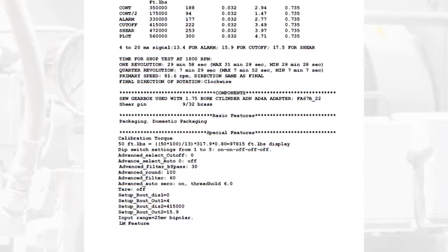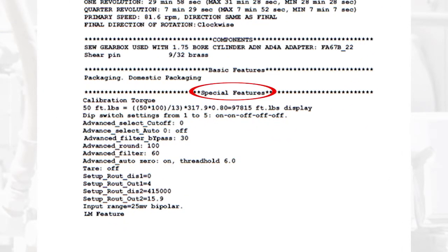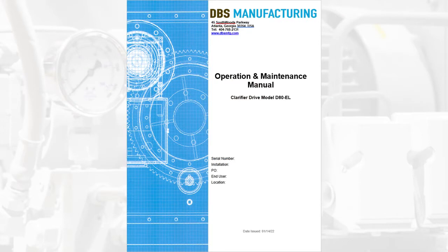The 2 numbers you will need are located under the Special Features section. The first is the amount of torque you will need to apply to the torque meter during calibration. The second is the value that will be displayed on the digital indicator when the torque meter reads the applied torque. This value will be different for each drive unit. Refer to your DBS O&M manual to obtain the specific calibration information for your drive unit prior to setting up the calibration procedure.